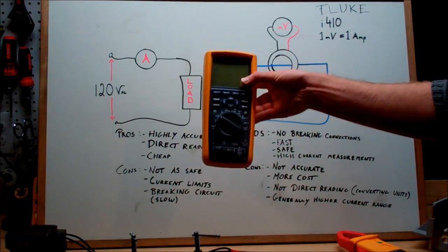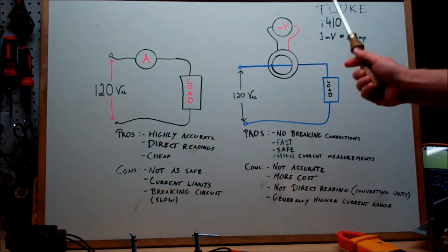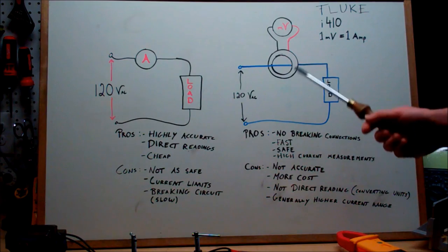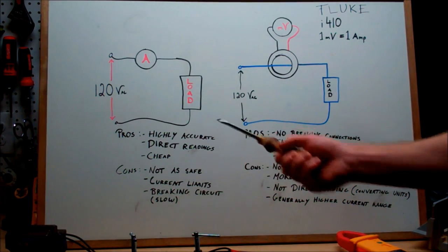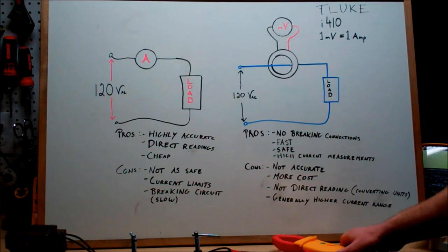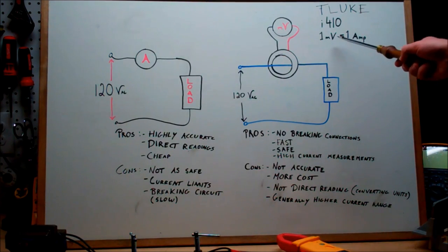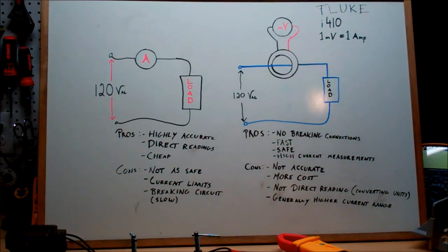Where if you use something like your current meter, your results aren't as accurate. Now you also get direct readings. And what I mean is when you're using a clamp meter, you don't have a direct current reading. You get a translation. And what I mean is you get millivolts. And for the current meter I'm using, 1 millivolt equals 1 amp. And now that is a really nice friendly ratio to work with, but not all of them have that ratio.